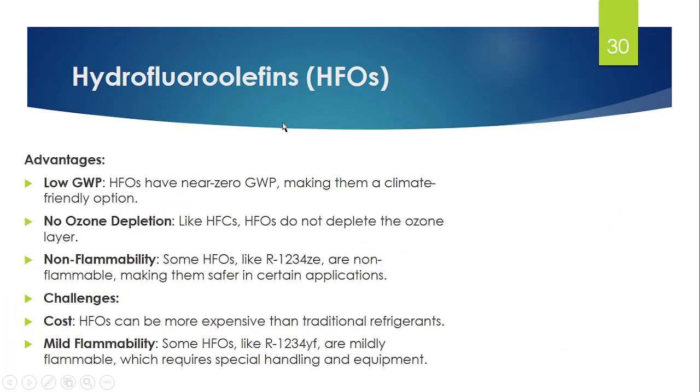So if somebody asks you what the advantages of hydrofluoroolefin are: the first advantage is that it has a low global warming potential, near zero. Second, it has no ozone depletion effect like HFC, and third, it is non-flammable. But what are the challenges you are facing? The first challenge is cost. The refrigerant system is becoming more expensive because of this synthetic gas. The second thing, which is less favorable, is that some hydrofluoroolefin types such as YF are mildly flammable. Not all types, some are.